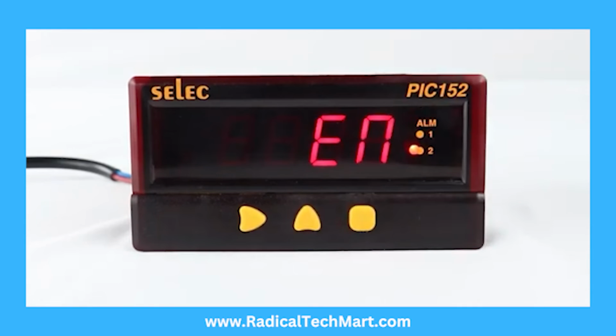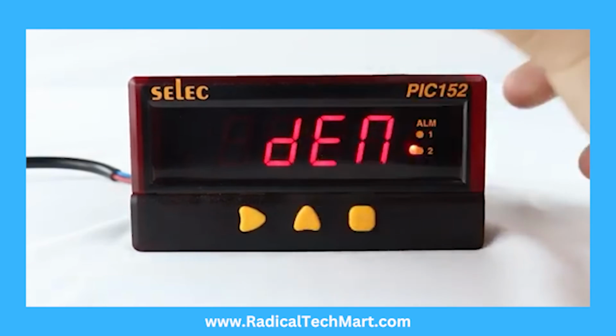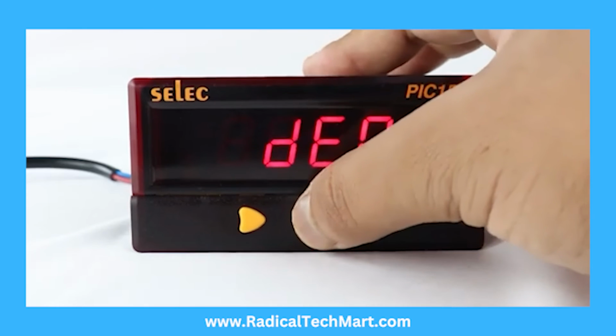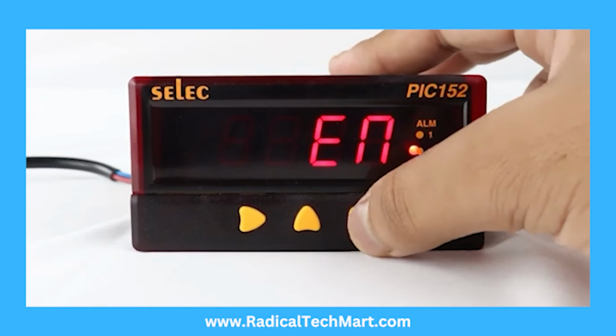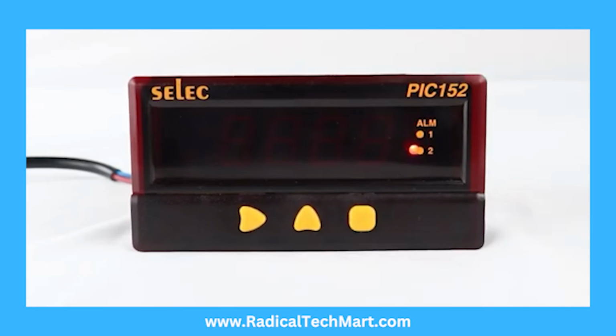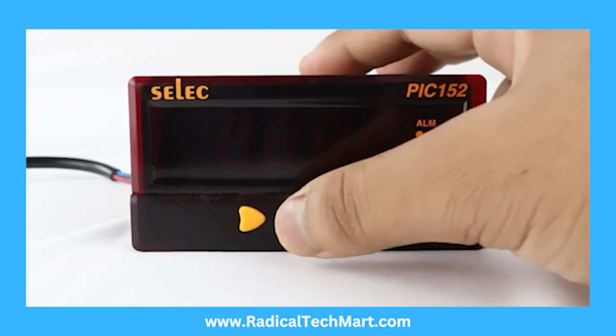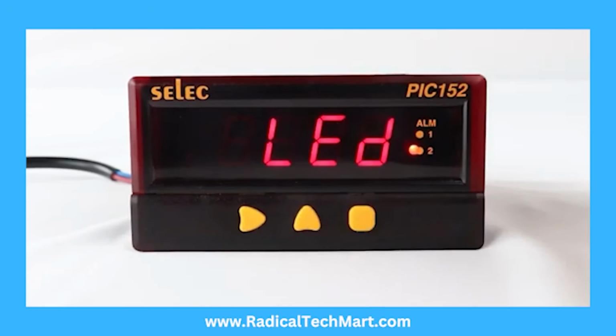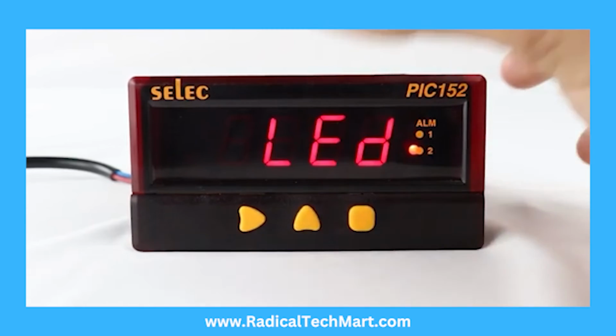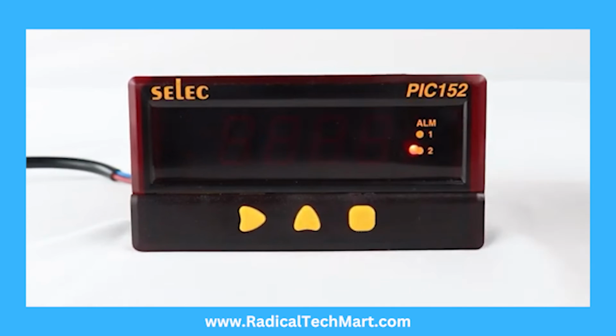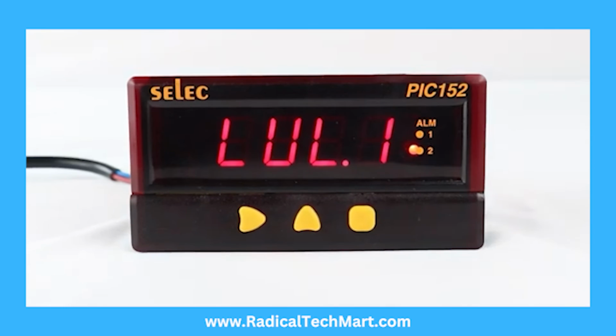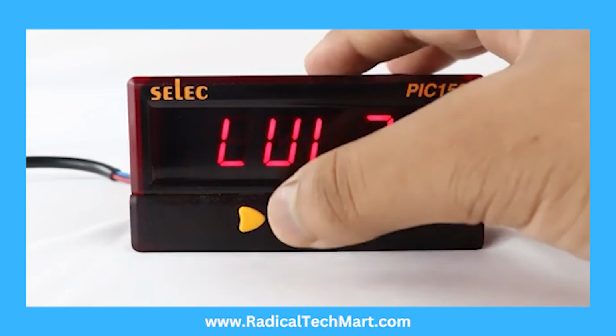Then press the square key to select relay status for alarm 1. Using the up arrow key we can switch between relay energized or relay de-energized. Press the square key to select alarm annunciator, whose function is to signal the presence of abnormal conditions by blinking LED. Then press the up arrow key to switch between LED and DSP as per the requirement. Programming steps for level 1 and level 2 are the same because both levels are being used for alarm output. Level 3 is for analog output selection.